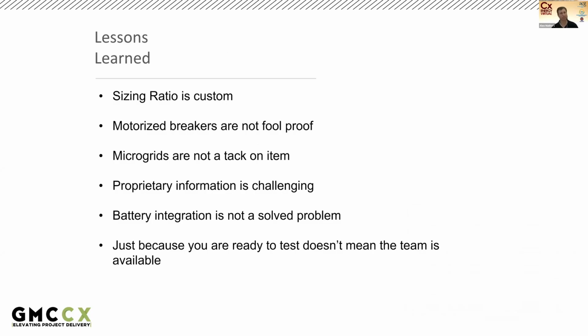Some of our lessons learned from this project. First, when designing a microgrid, the sizing ratio between the battery and the power generation is custom. It needs to be engineered and optimized. My understanding is the battery is typically sized from 1 to 1.5 times the generation capacity. In this case, the battery was sized a bit under, I think, 1 times the generation, but again, that's a custom and engineered sizing ratio.